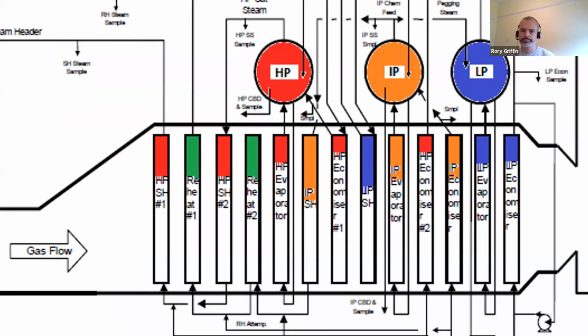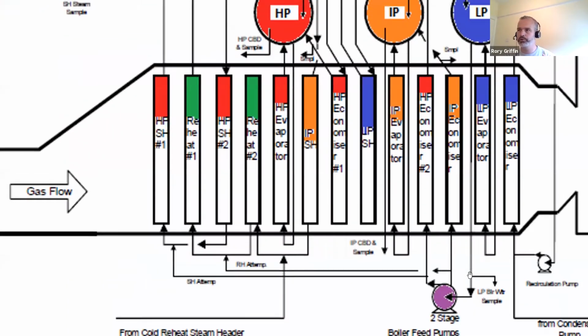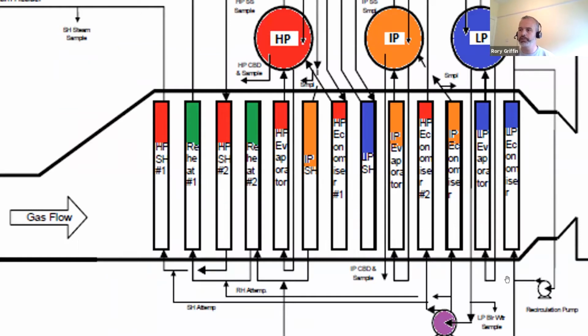So again, apologies there, I definitely colored this in myself. What we'll do is I'll just trace the water flow through the boiler, and you'll probably get a better appreciation then. So at the air-cooled condenser, the large fan structure, we've converted the steam down to condensate. The extraction pumps will pump, and it's typically maybe 420 to 440 tons per hour up to the boiler.